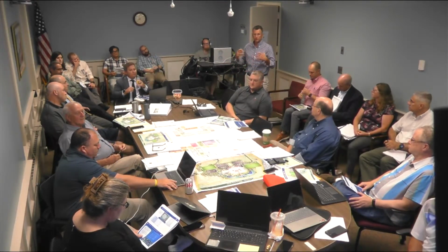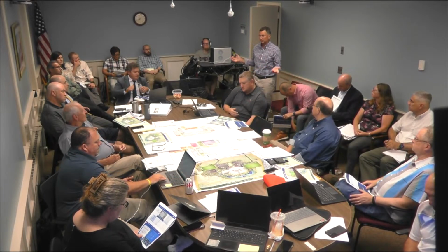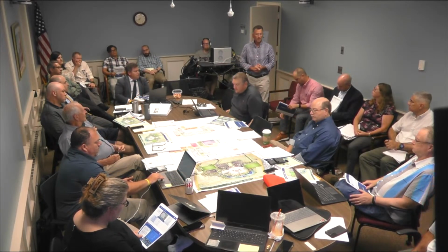Our push is really to focus on the chilled beam because it gives individual controls throughout the school, except in large areas where it wouldn't be appropriate. It couples with either system — the system will be driven by budget, and the radiant floor will be looked at from a cost perspective. The dedicated outside air system works for everything and gives the best IAQ for the building since we'll always have fresh air exchange. The control system will be integrated with either ALC or Distech, whichever it may be, and we're targeting an EUI around 25 — the lower we keep it below 25, the more incentive you'll get from Eversource.